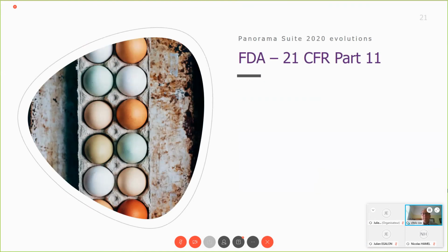Another thing we've done for Panorama H2 is we brought it under the umbrella of FDA 21 CFR Part 11. Now, for those of you who don't work in the pharmaceutical or the medical device or the food industry, FDA is the American Food and Drug Administration, and they have a series of titles that they write. They call them titles. So they have a number of titles of their Code of Federal Regulations that people have to adhere to. Part 11 of Title 21 is all about electronic signatures, electronic records, and what you've got to do with them when you replace paper records with electronic versions.